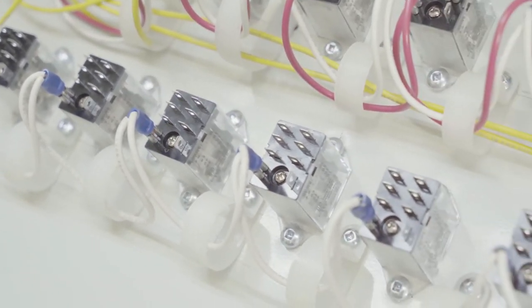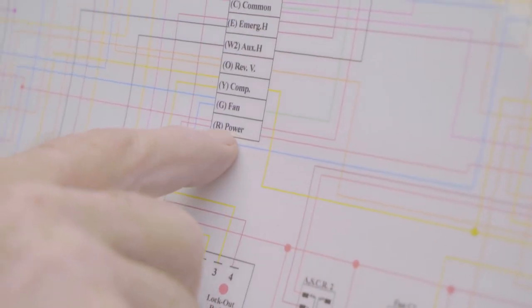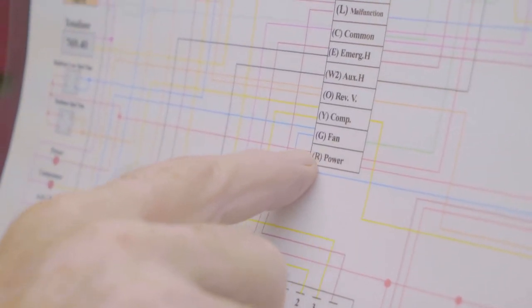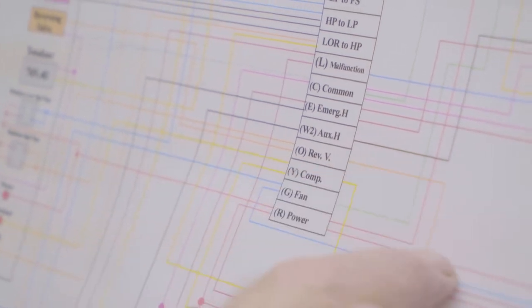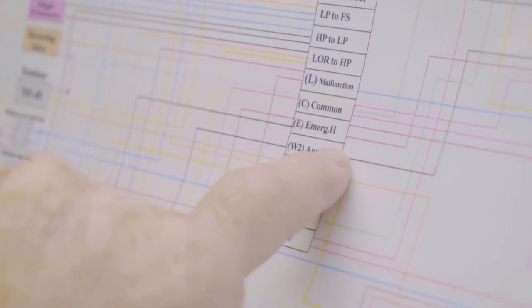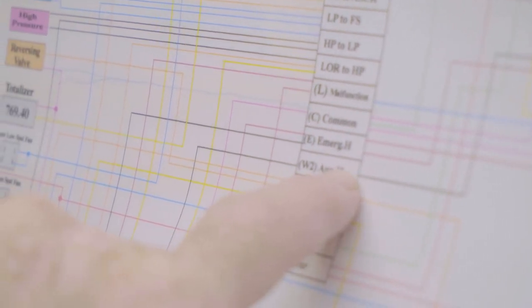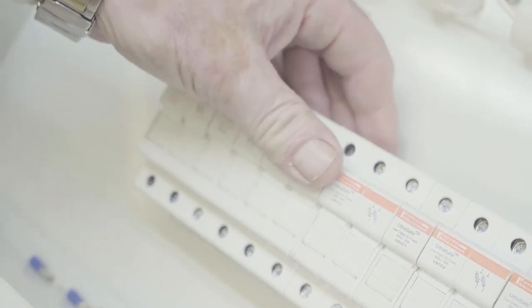All the wires — as opposed to other units where they all have one color — all our wires and systems are color-coded: red for resident power, white for common, yellow for compressors, blue for fan motor, brown for emergency heat, black for Y2, a second-stage compressor. We use finger-safe fuses so that they're totally safe.